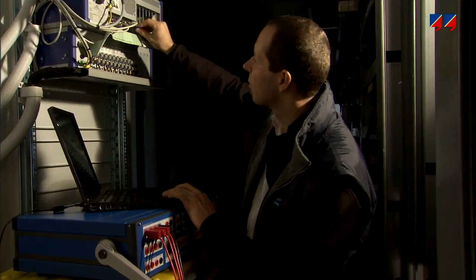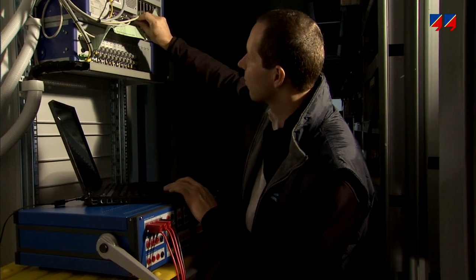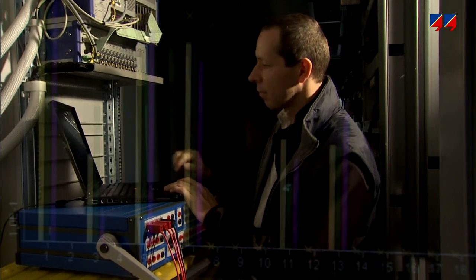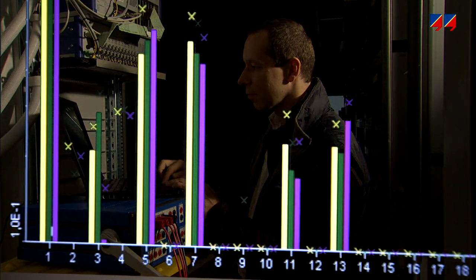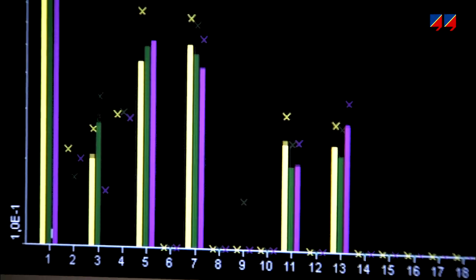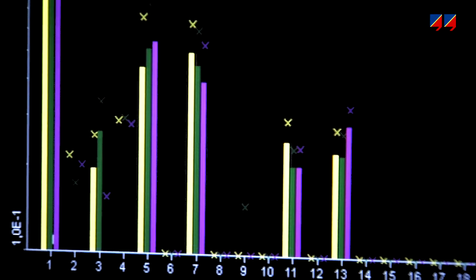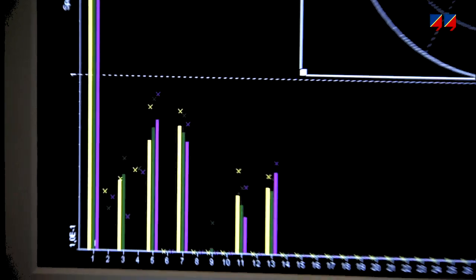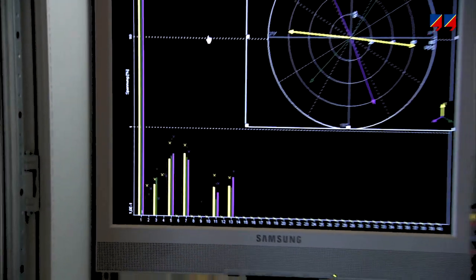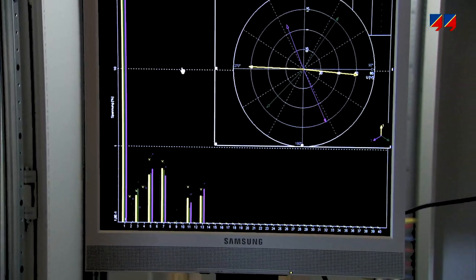Additionally, the CMC 256 Plus is ideal for testing power quality devices, which normally require precise voltage sources, but also in some cases, precise currents. The maximum output frequency of 3 kHz for all voltage and current outputs provides sufficient performance to cover tests with harmonics as defined in the relevant IEC or ANSI standards for 50 Hz or 60 Hz networks.